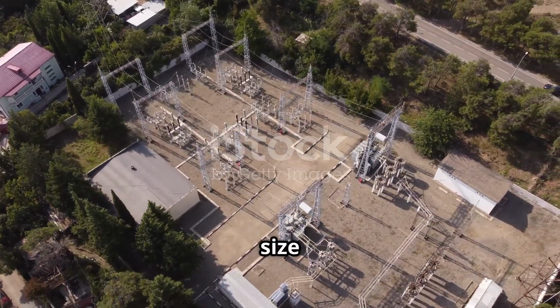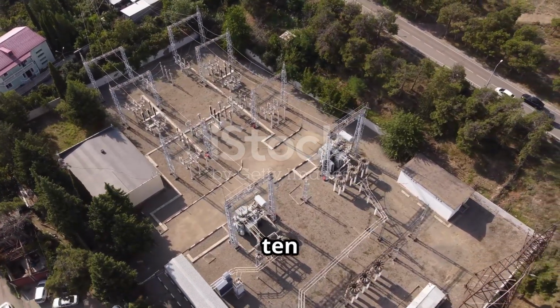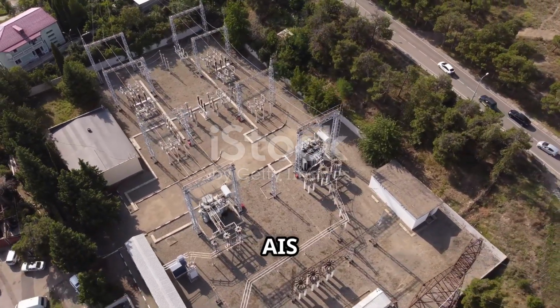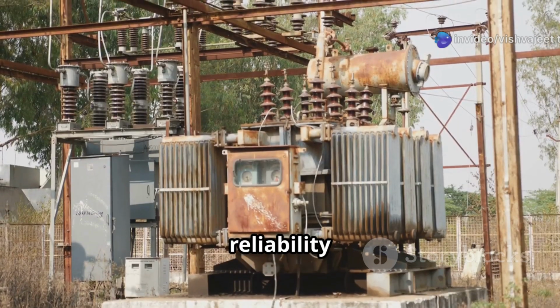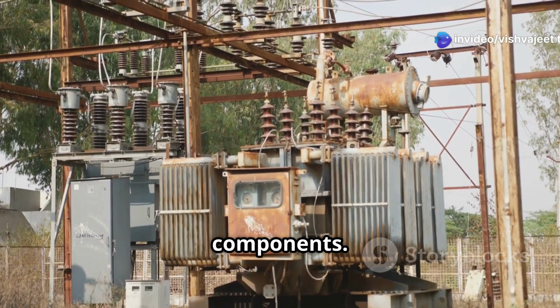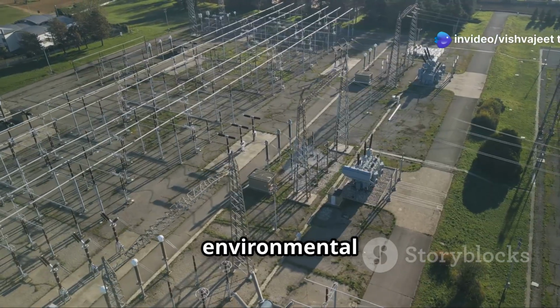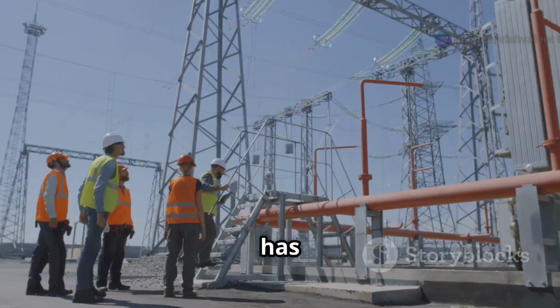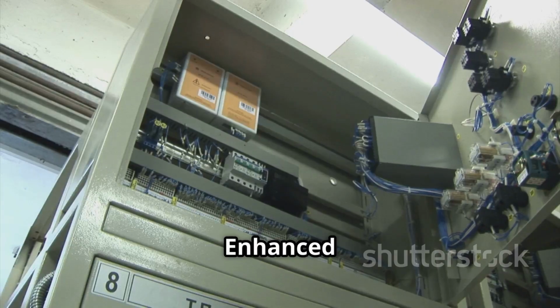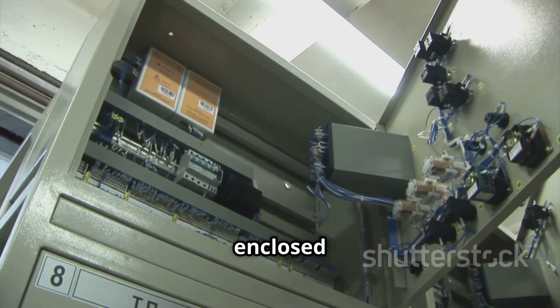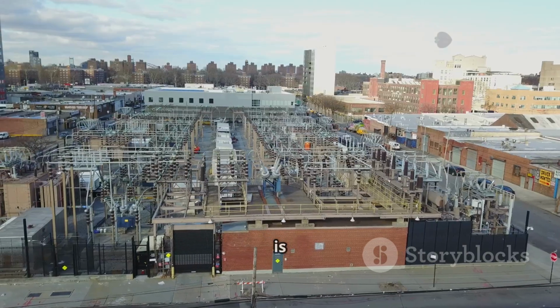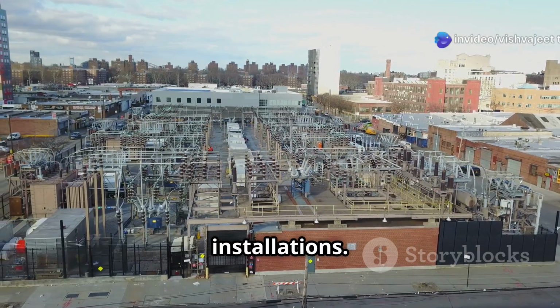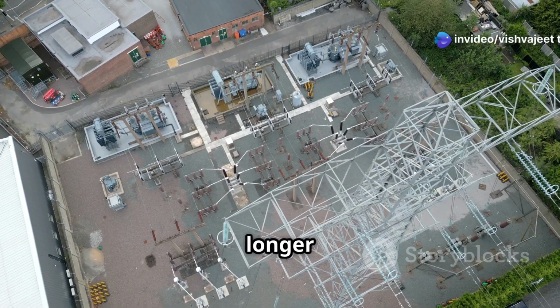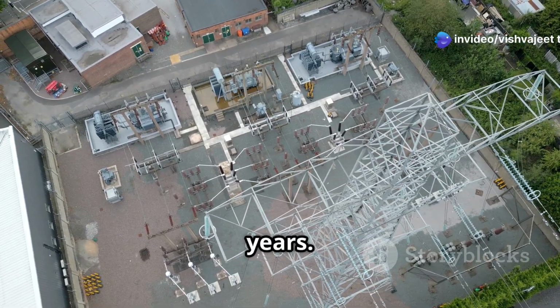The compact size of GIS requires only 10 to 30% of the equivalent AIS footprint. It offers high reliability with protected components. GIS has minimal environmental impact on performance. It also has lower maintenance requirements. Enhanced safety is achieved with enclosed live parts. GIS is suitable for urban and indoor installations. Lastly, it has a longer service life, typically 30 to 40 years.